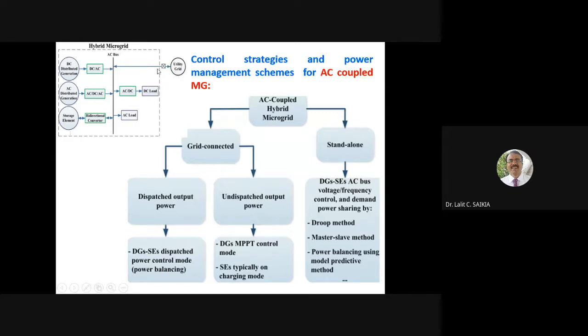In this case, it is grid connected, so the AC bus voltage and frequency are in general maintained by the utility grid. The frequency and the magnitude of the voltage are maintained by the utility grid in grid connected mode. In standalone mode, the utility grid is not connected, so we have to maintain fixed AC voltage and fixed frequency here. This should be done by controlling these converters.